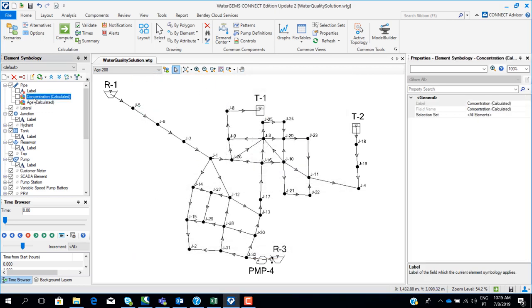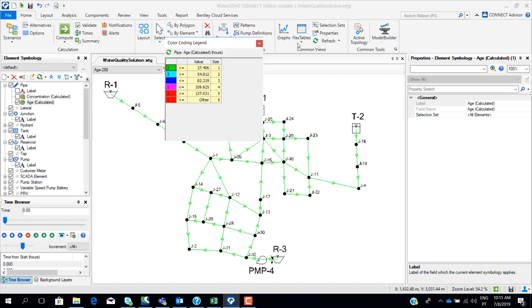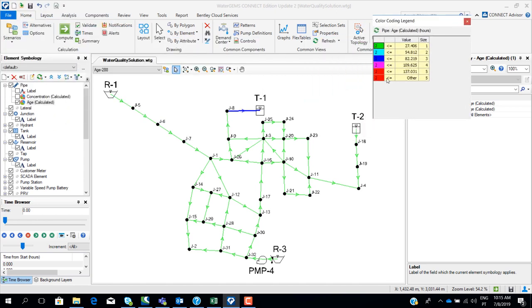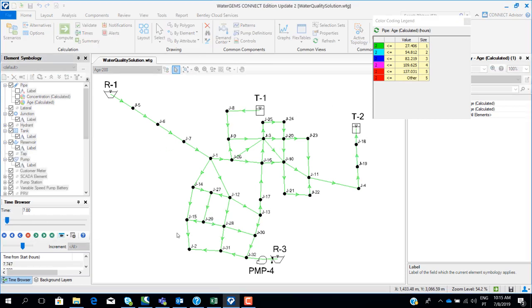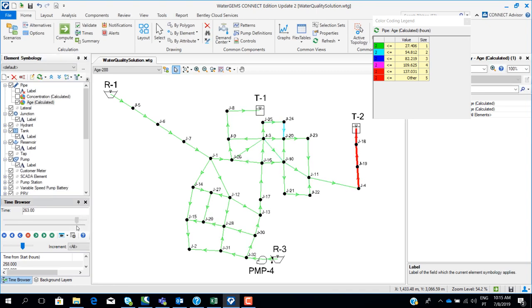We have to turn on another property — age — in the pipes. Let's open the legend. The values are in hours; red is more than 137 hours. Playing through the simulation, we can see that higher ages are near tank one and two as the simulation progresses. Near tank two we can achieve a time in the network bigger than 137 hours.